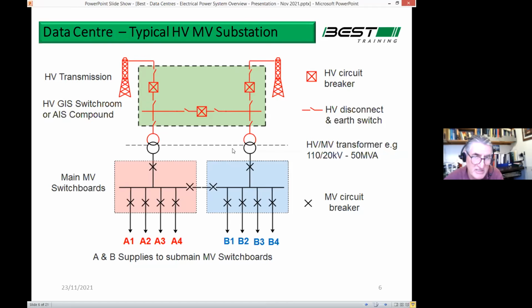So you have the transformers here transforming power down from 220 kV or 110 kV down to 20 kV. Those transformers are typically 50 megawatts each, which is enormous. It's the size of a large town that will be taking that sort of power. And then the supply comes out at medium voltage, and you come into an A board and a B board.